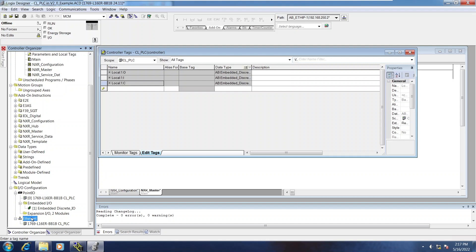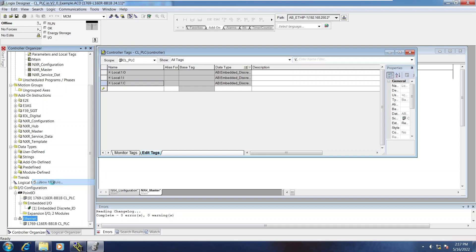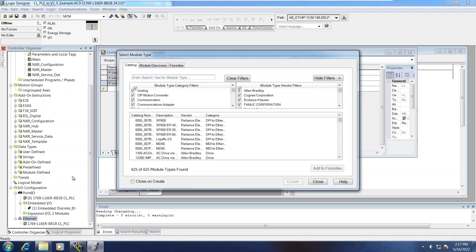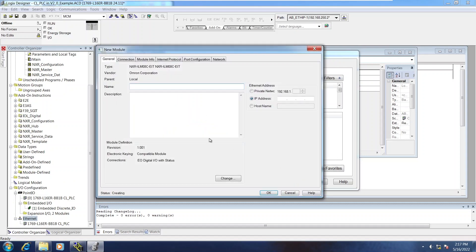Now the order of which we do these things is important. So this is the first video out of three, and it should be followed in this order. The first thing will be to create a new module on the Ethernet port that the NXR is connected to. I have pre-installed the EDS file for this. Go ahead and search for the NXR and create it. It will need a name.